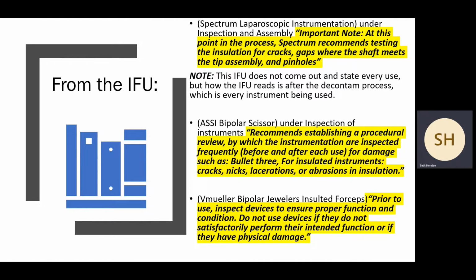That is in the prep and pack section, the assembly and inspection section of the Spectrum IFU. Here's another thought. Do you test all your lap instruments? Great. You test your coated bipolars as well. These are electrosurgical devices. And by the way, ST79 doesn't say laparoscopic instruments. They get very generic on purpose, because anything coated is supposed to have the same performance, that it contains electrosurgical energy from where it enters the device to a specific point, mostly the tip, where it is supposed to get out to perform cauterization, and nothing in between.